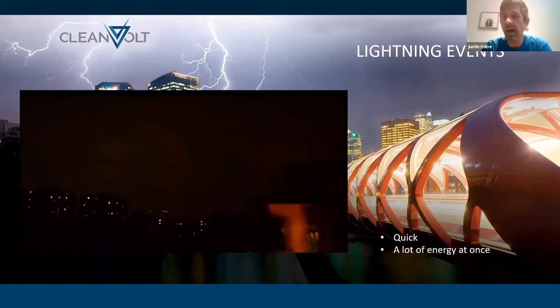As you can see with lightning events, they're very quick. It's a lot of energy all at once. Like in this video, the Canadian Electrical Safety Authority states that 80% of lightning-induced damages come in through your main service. That's usually due to a strike somewhere in your general area. But of course, lightning events are fairly rare. It's not uncommon to have a room full of 50 electricians, and we'll ask them by a show of hands how many of you have customers that have been impacted by lightning in the past. And it's very typical to see less than 5 hands go up out of that room of 50 electricians. So it is a very damaging event, but of course they are rare.